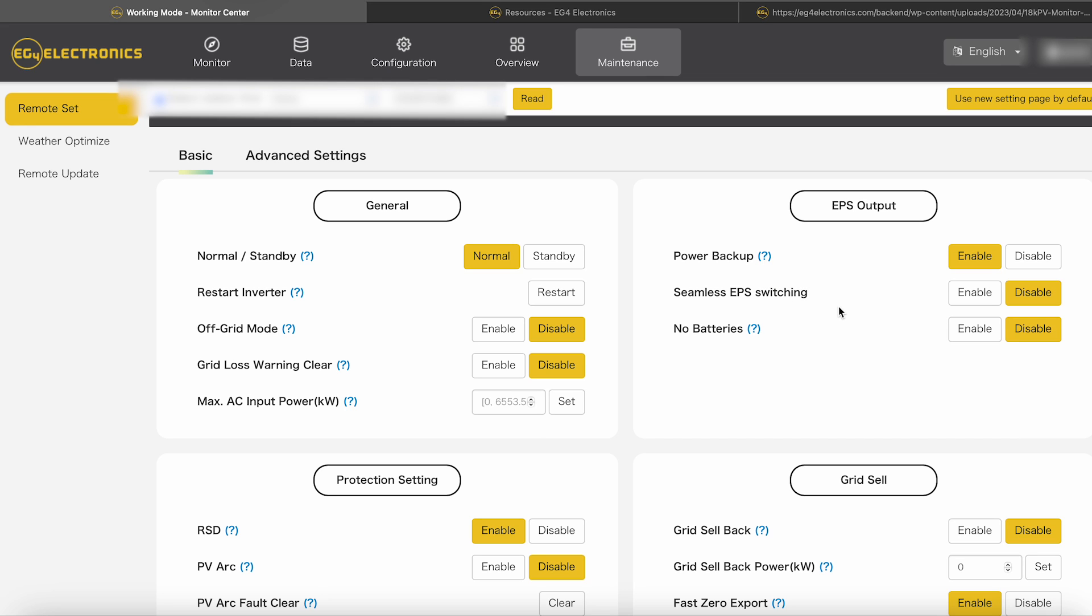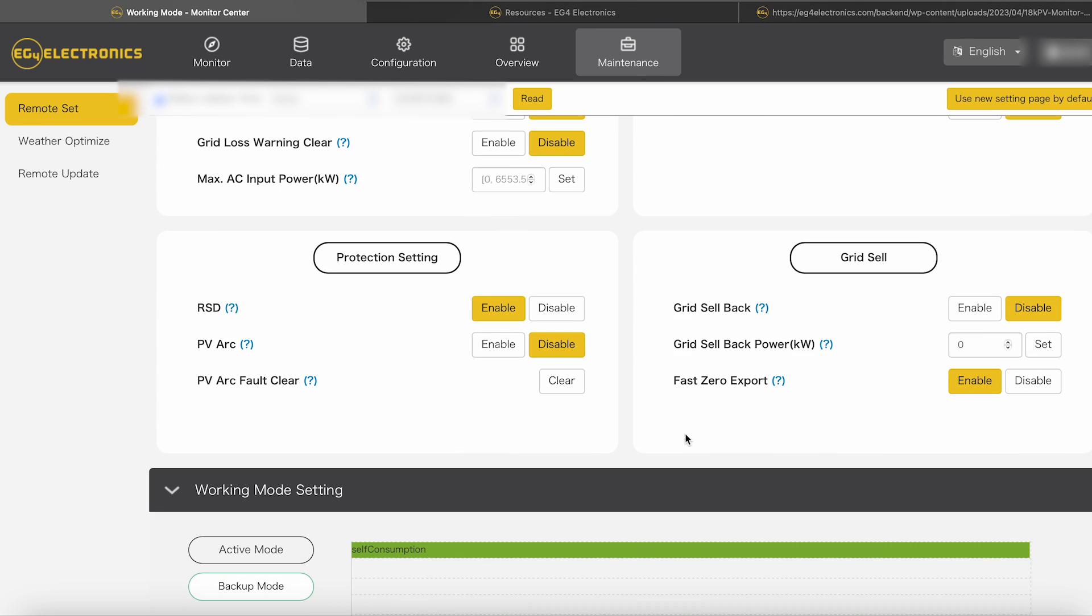Let's say the grid power goes down, instead of that thing shutting down your inverter, it's just going to use your battery backup to power your partial backup load panel. And then EPS switching, I got it disabled, no batteries, that's disabled. Off-grid mode, disabled. Grid loss warning is disabled. Let's see, grid sellback, I got that disabled because I'm not selling back to the grid. So that's very important. You don't want to have that set if you're not able to sell back to the grid because you don't have your correct permits and your authorization from your power company to sell back.